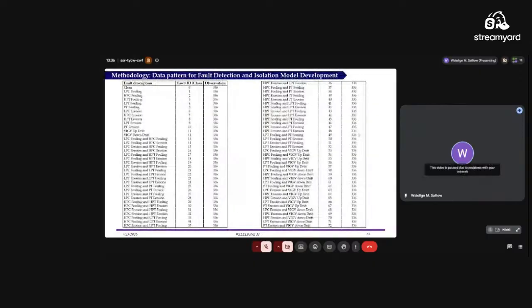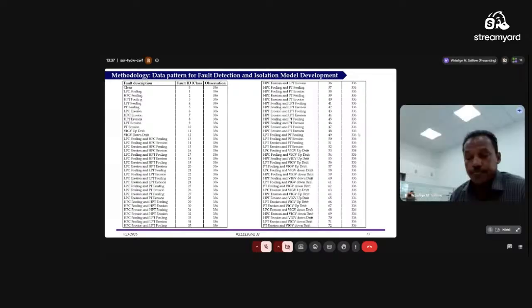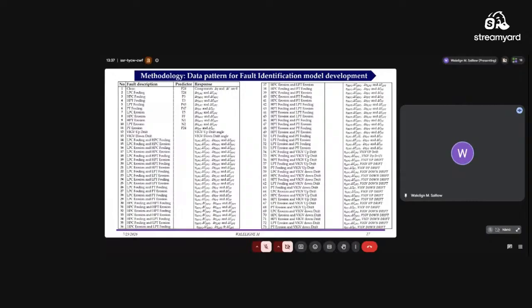So this one is the labeled data, to detect and isolate the faults, so fault detection and isolation. The second module is fault identification. In fault identification, we have performance indicator parameters, the flow capacity and the isentropic efficiency. So the predictor is to predict those performance indicators, the flow capacity and the isentropic efficiency. Those two parameters are the performance indicator parameters in a gas turbine. The predictors are station parameters at each station.